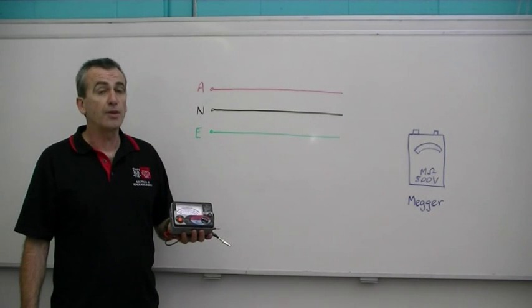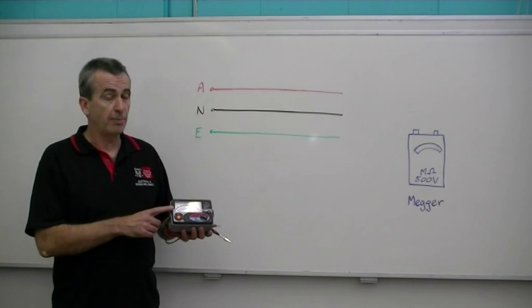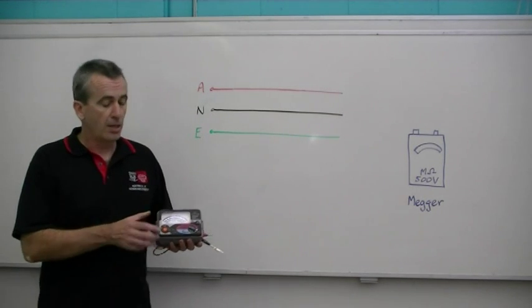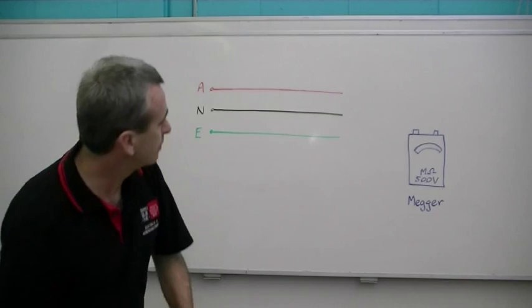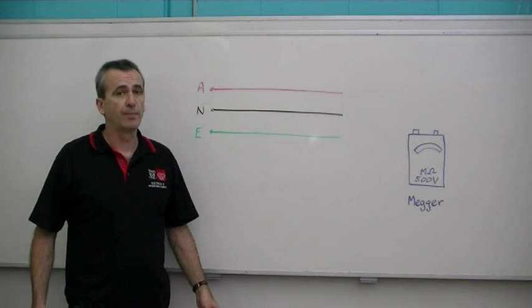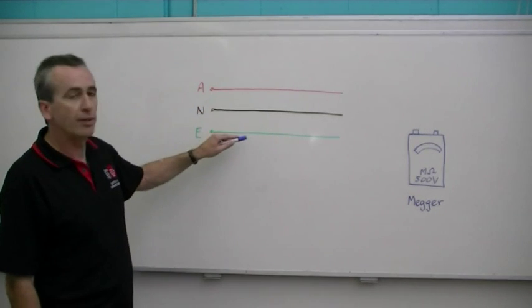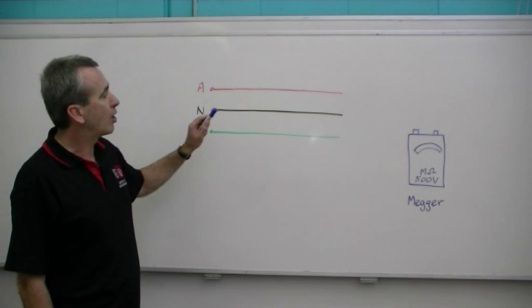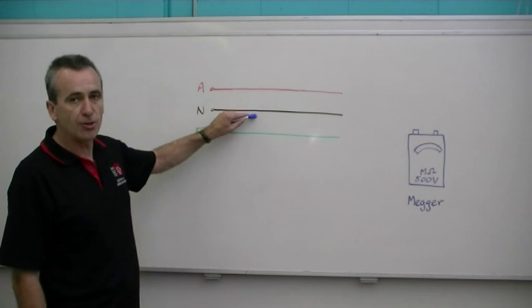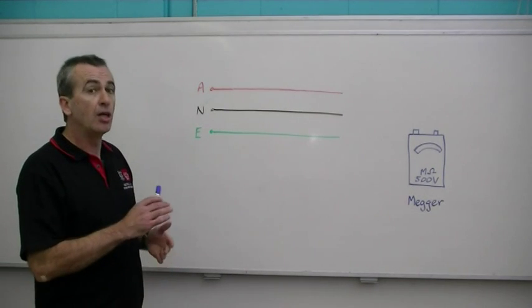The Australian wiring rules require that you must test the insulation resistance of all wiring before you connect it to the supply. That means we have to do an insulation resistance test using the Megger. This test is between live conductors and the earthing system. The live conductors are the active and neutral conductors, and the insulation resistance test is measured between those live conductors to earth.